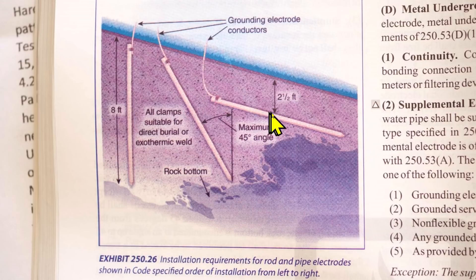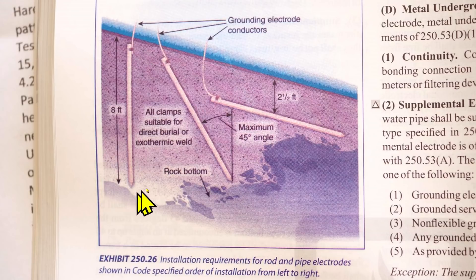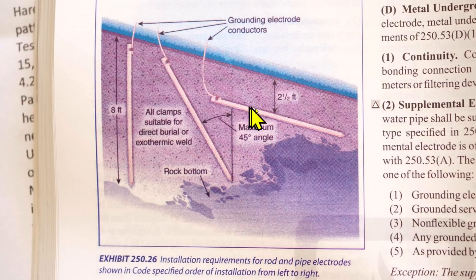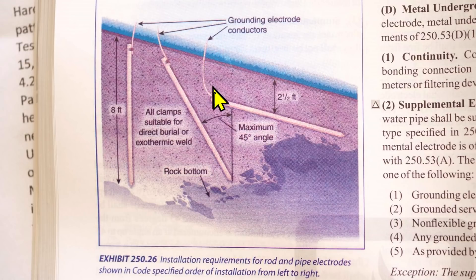Or you can dig a trench two and a half feet deep. I have a story about this: I installed a panel one time and I could not get my ground rod to go straight down, so I dug a ditch — you can call it a trench — two and a half feet deep. I put my ground rod down there, or you call them electrodes actually. This is an electrode, and I hooked up my grounding electrode conductor to my electrode ground rod.